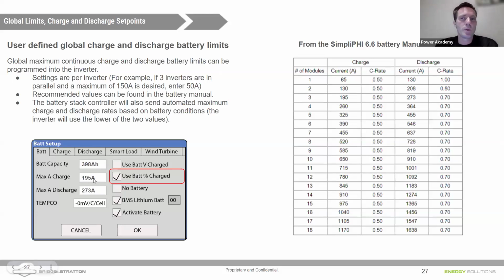So for a 3-stack, it'd be 195. If you've got a different number, maybe you've got 6 batteries or 9 batteries, you can look on this table to see what maximum value you could put. Now this is per inverter, and the maximum value a Sol-Ark 15K inverter will do is actually 275. So if you've got a 6-stack of batteries on a single Sol-Ark 15K inverter, the max value you would put here is just 275. That's the highest that you could go to.